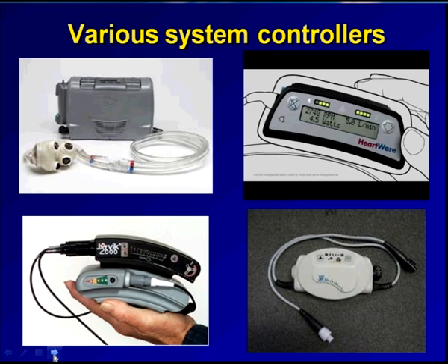To try and remember exactly how each and every one works and what information they're conveying may be complicated if you don't deal with these devices every day. But just do realize that this controller is a venue for power to the device inside the body, so we don't want it disconnected, and it's connected to some type of power source. And if there's a problem with that power source, go to this controller to tell you that that's part of the problem that you may be encountering.